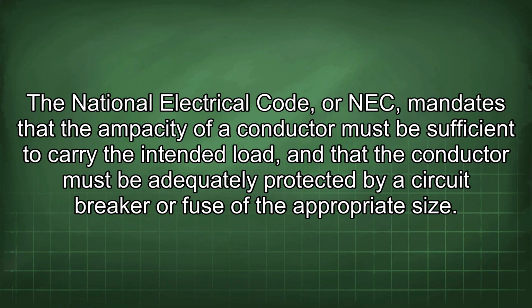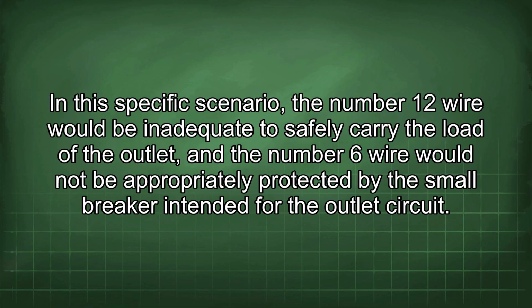The National Electrical Code, or NEC, mandates that the ampacity of a conductor must be sufficient to carry the intended load, and that the conductor must be adequately protected by a circuit breaker or fuse of the appropriate size. In this specific scenario, the number 12 wire would be inadequate to safely carry the load of the outlet, and the number 6 wire will not be appropriately protected by the small breaker intended for the outlet circuit.